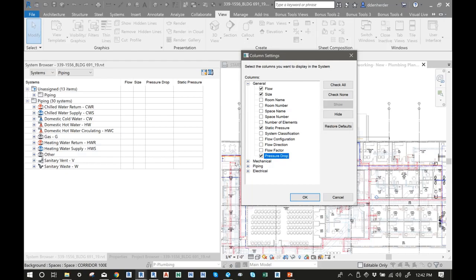But the thing is, you can still get good information even if you can't get static pressure or a pressure drop, which are kind of the big numbers for determining and selecting equipment. You can still get things like friction or flow that you can use for sizing pipes and ducts, and I've used that to help out engineers.